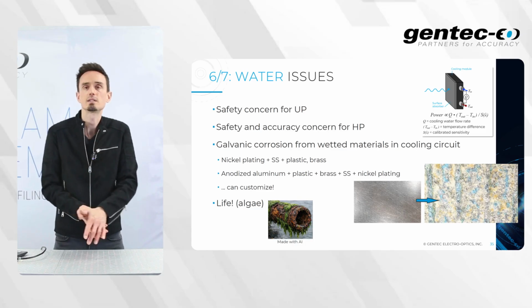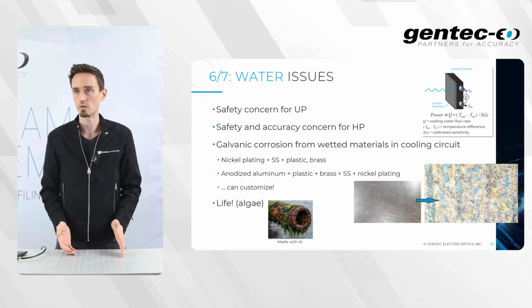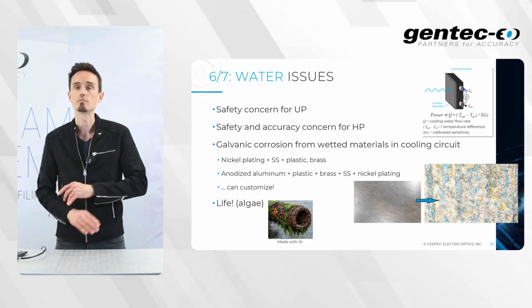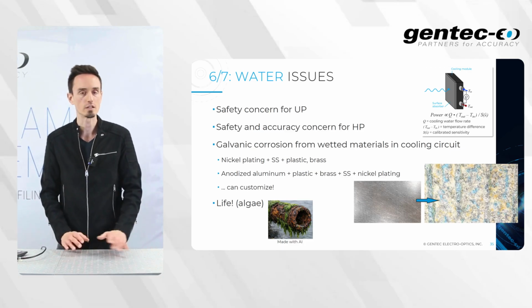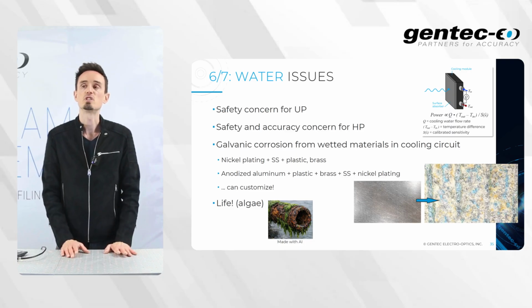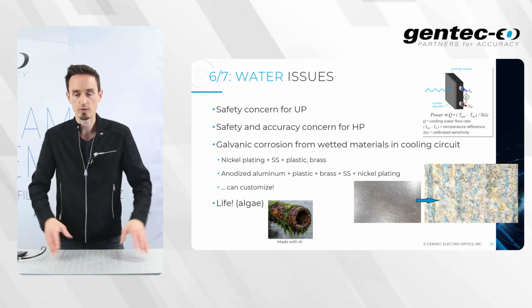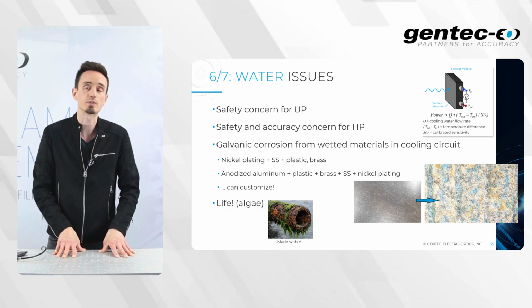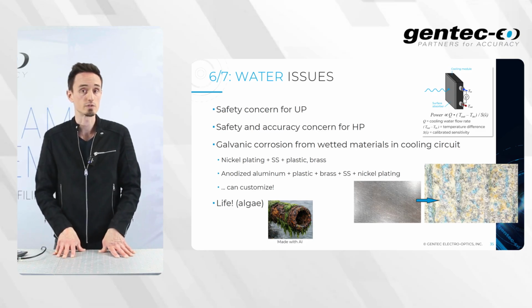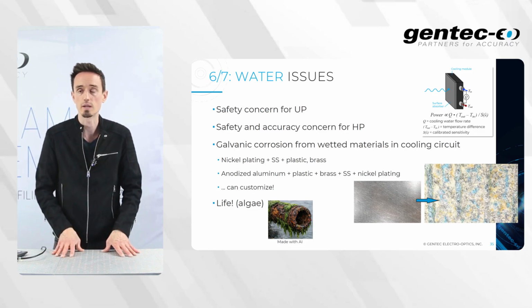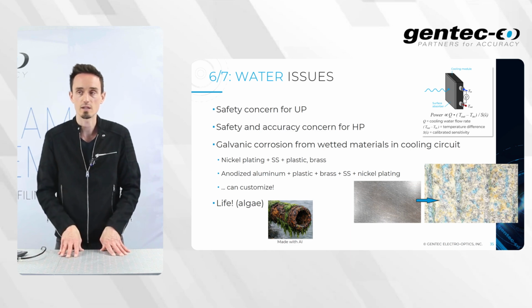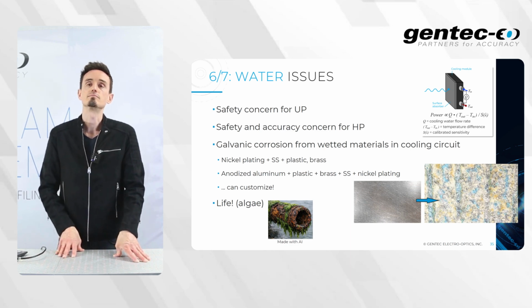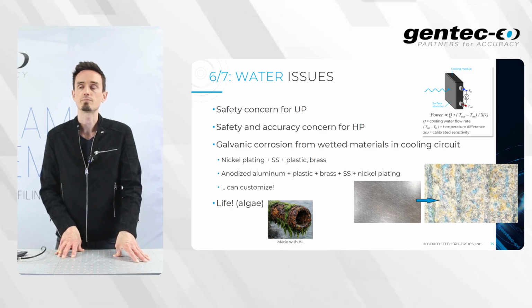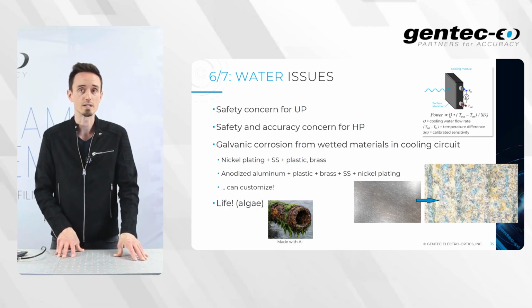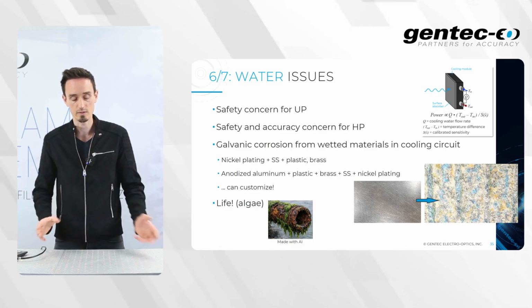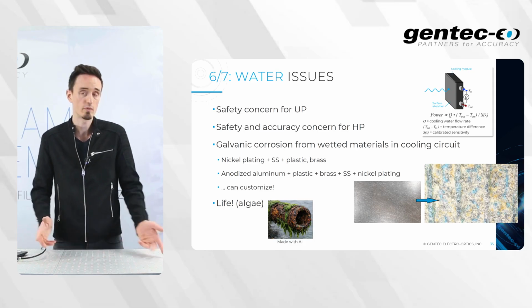The main issue here, as you could guess, is galvanic corrosion, right, from wetted materials in the cooling circuit. Whether that's, as you could see, those materials, nickel plating, stainless steel, brass, and so on. Typically, we provide those lists for you to evaluate that, and we could customize potentially if you see materials here not compatible with your water lines and chillers and so on. The picture you see with the arrow, that's going from nickel-plated copper. Yep. After a while, in some bad situations, that was totally corroded, and we have to pretty much change everything in this case.